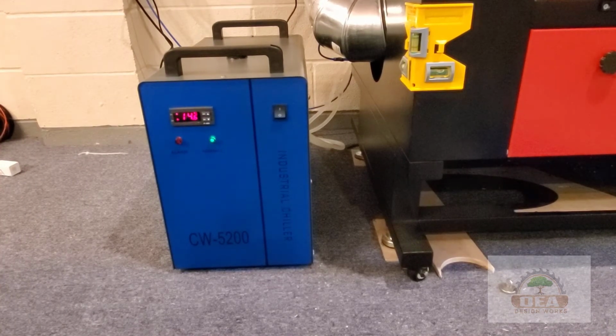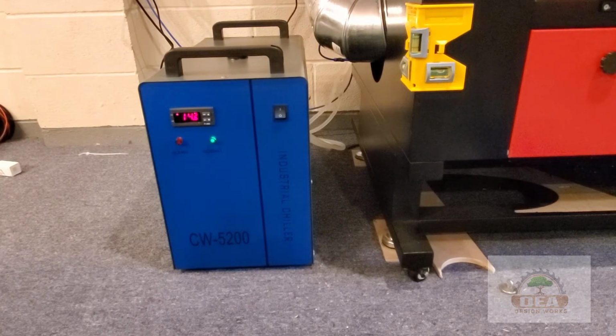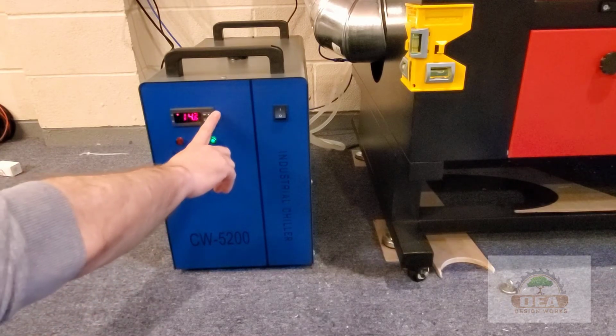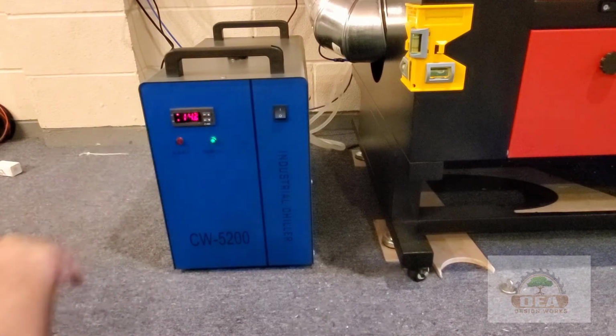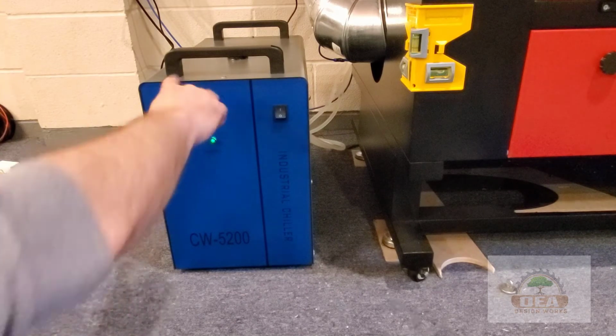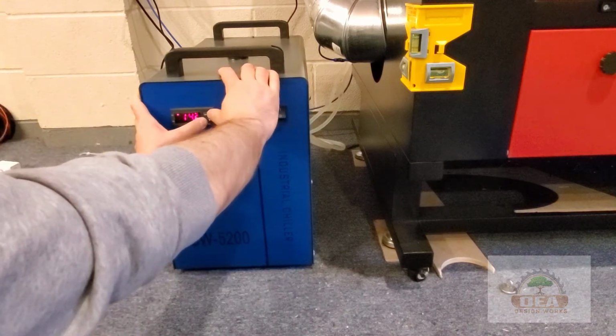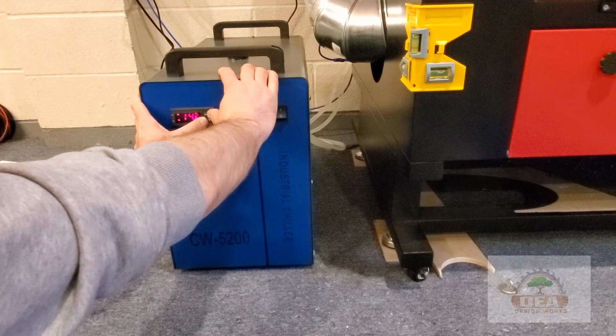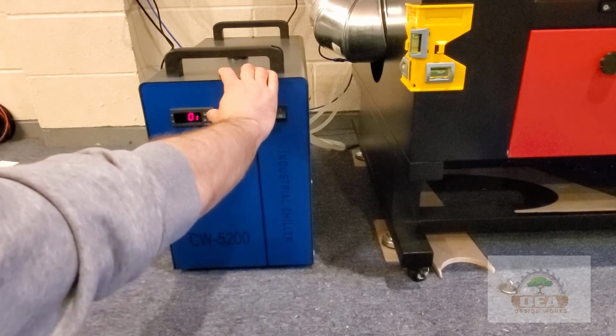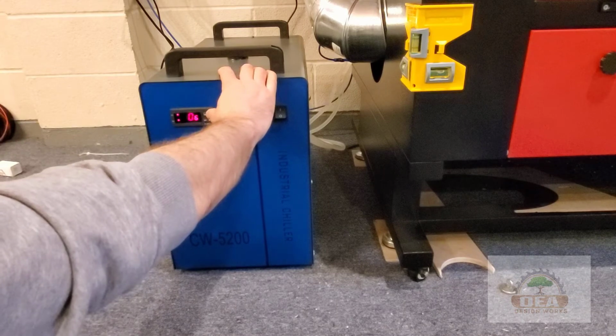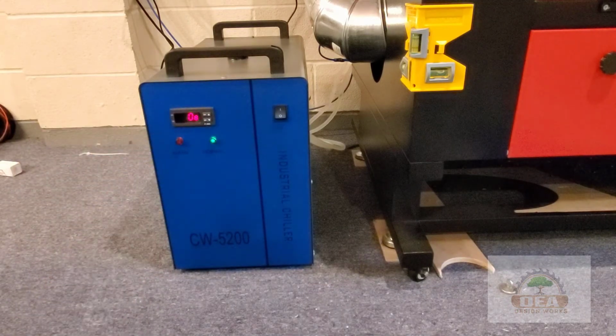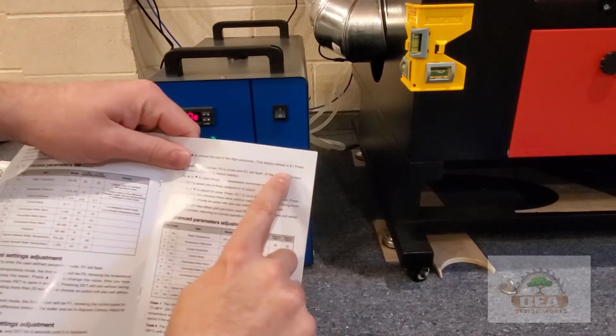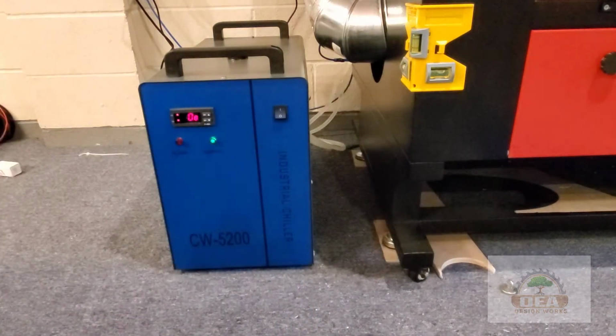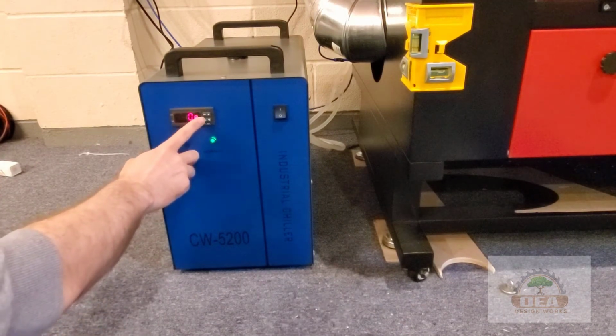Okay, so now we need to enter a password to be able to do some changes in the settings. So I'm going to press the up arrow, the right side of the top one, and the set, which is the lower side, the left side of the lower one, and then I'm going to go ahead and get it until it shows a 0. So there's my 0. If I continue to press the up arrow, I'm going to go to 8, which should be the default password. It does show it in the book here. Mine, it shows right here, it says the factory default is 8. And I'm going to go ahead and press set.